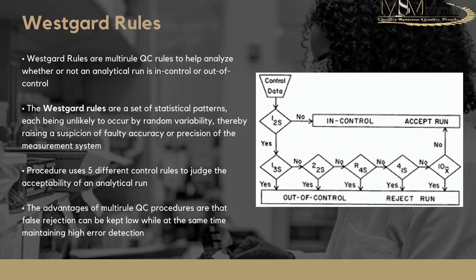Westgard rules are multi-rule QC rules used to analyze whether an analytical run is in control or out of control. They are a set of statistical patterns, each being unlikely to occur by random variability, thereby raising a suspicion of failed accuracy or precision. Because some error is random, when you get a failed QC result you would first repeat the run to rule out random error. If it still fails, you analyze the results, plot the data, and determine whether you have an accuracy or precision problem before performing a root cause analysis.